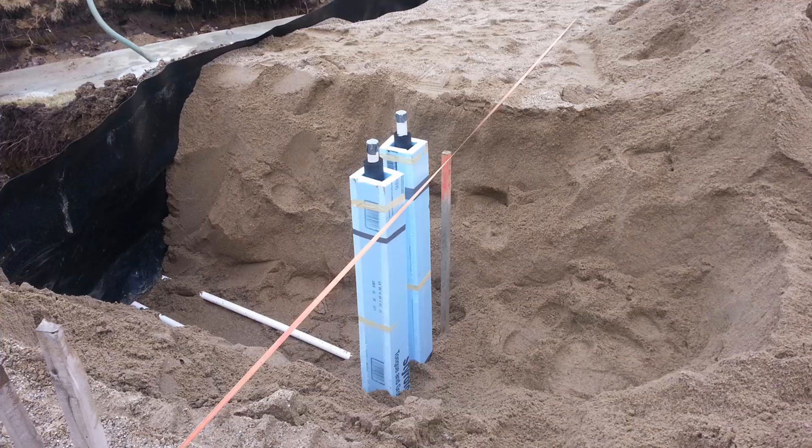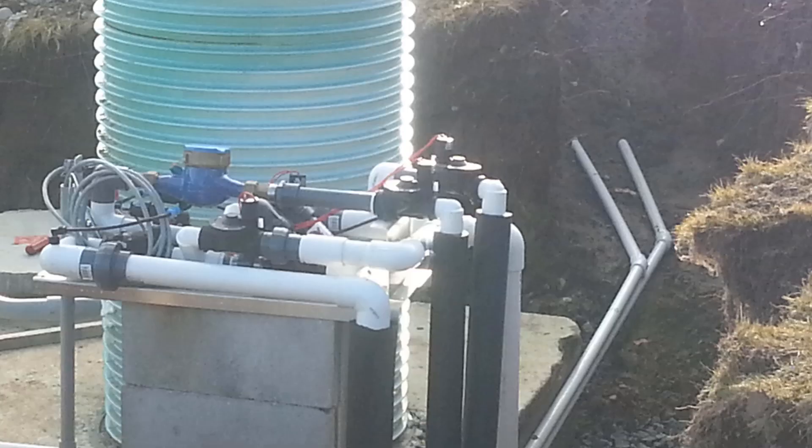Here is the black Armaflex insulation wrapped around the 1 inch pipe. Note that the force mains are below frost — where they elbow up to come through the frost zone is where we're going to insulate it, both with the Armaflex and then using the 1 inch rigid foam cut into strips to make a box. Here you can see that same Armaflex insulation used for the risers that go from the hydraulic unit down to the 1 inch supply and return lines.